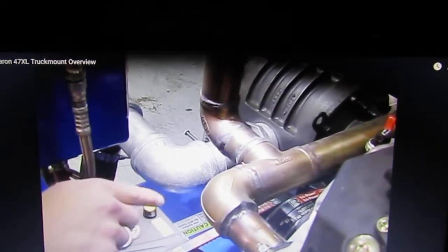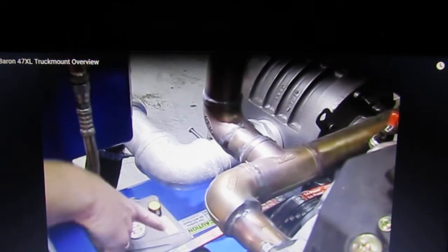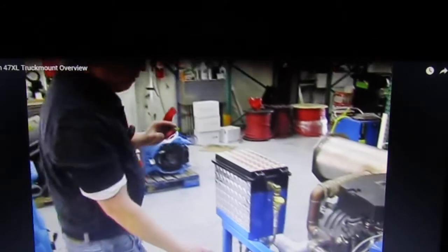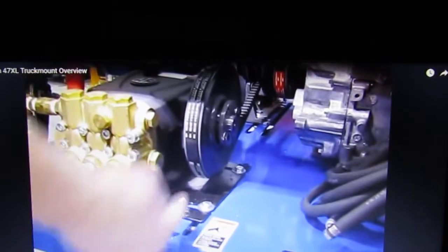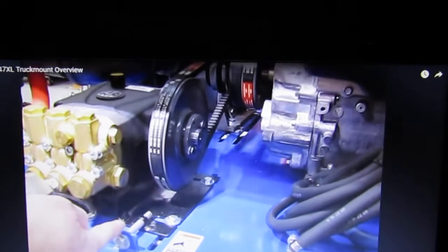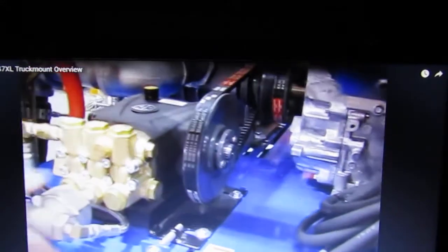The other really neat feature about this particular design is the BX30 belt that's being used for the pump is the same belt number that's being used for the vacuum pump. So you only have to keep in stock one belt number, and it's not like you're carrying a bunch of different belts for one machine. Just one belt is all you need, one belt number. The other thing that he's designed here is a real nice feature for tightening the belt. So there's a built-in belt tensioning system here. And we have our pulsation pump. This is a last step chemical injection pulse pump that they've added on here.